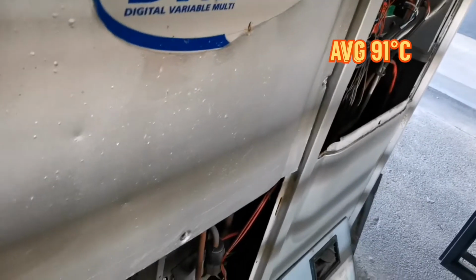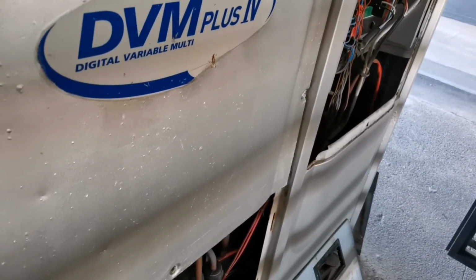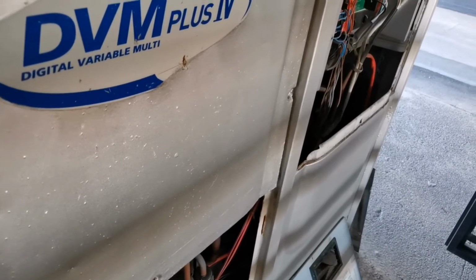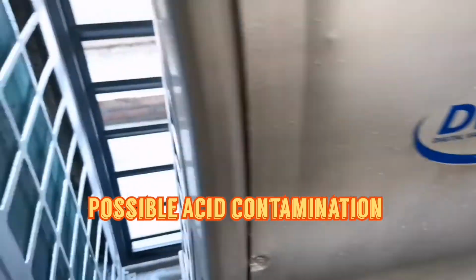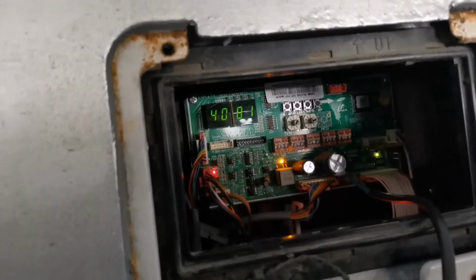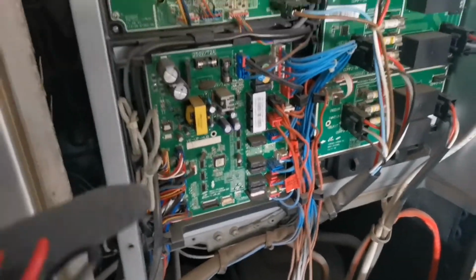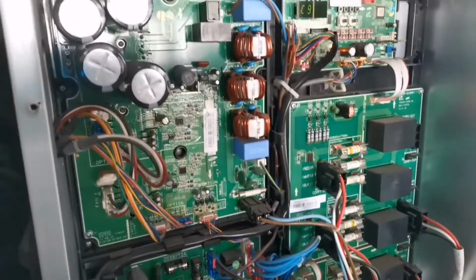The thing that did concern me was my discharge temperature. Discharge temperature was over 100 degrees Celsius. It came down to about 96 degrees. Right now it came down even more, but that is a concern. The pressures are looking good, but that's a concern because of contamination. We potentially have contamination in the system, so we will have to have a close look at that. As you can see, low side pressure is about 8 bars right now. So I guess there are some more quotations to go out.